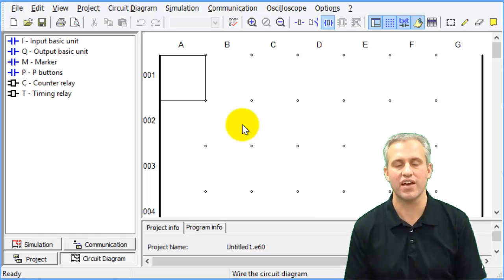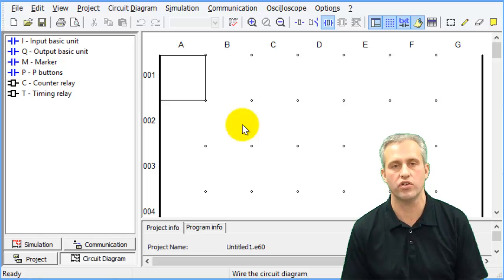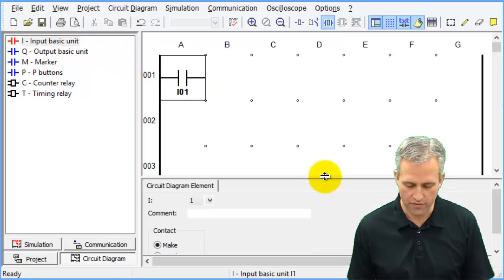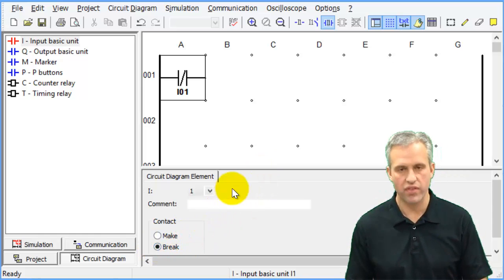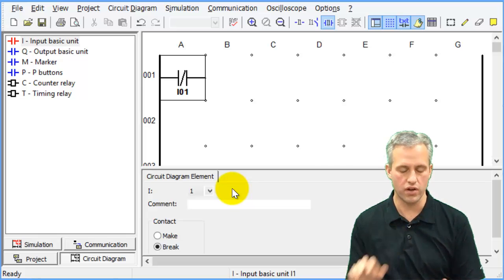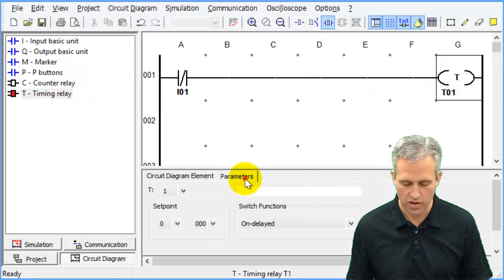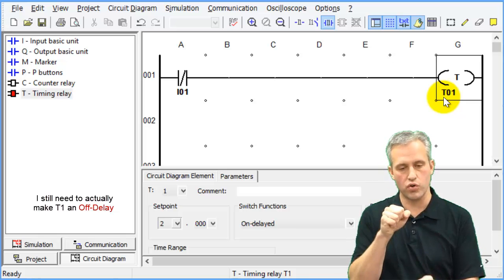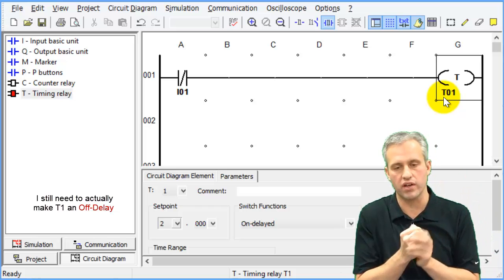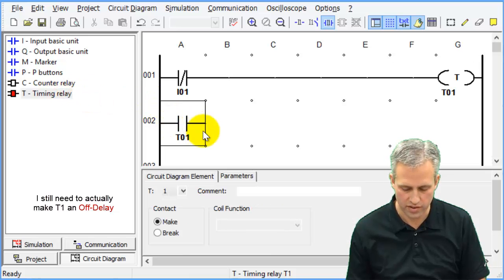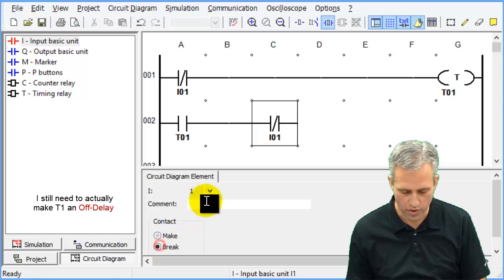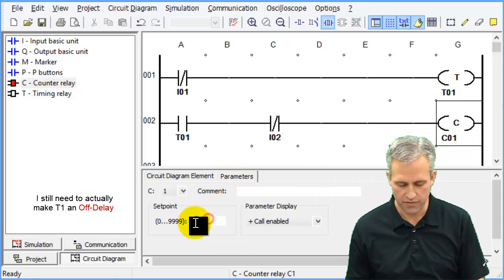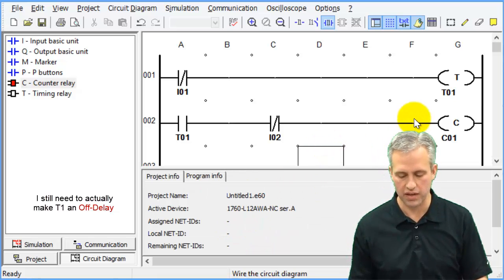See what you can do on your own before we solve it together. I'll solve the count-up situation first. If I1 becomes broken, that begins a 2-second interval window. My approach here is to kick off a timer — a 2-second off-delay. As soon as you release, you've got a 2-second window. If, while T1 is high, you have a break on I2, then count up. Count-up is easy — just drop it in, set point of 1.